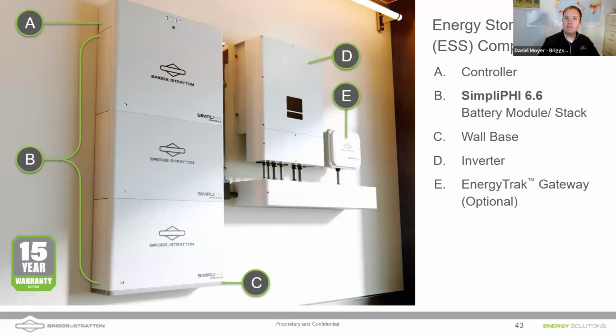Every system is going to need the following components. You're going to have a stack of batteries. You can go up to 3 batteries in a stack, and you can have up to 6 stacks in a system. Each stack is going to need a controller on the top. This is where the power button is, this is where the fuel gauge is, and this is where the home runs come out of the battery stack and flow into the inverter. That's the power and the communication. That's letter A. Below the controller are our battery modules.